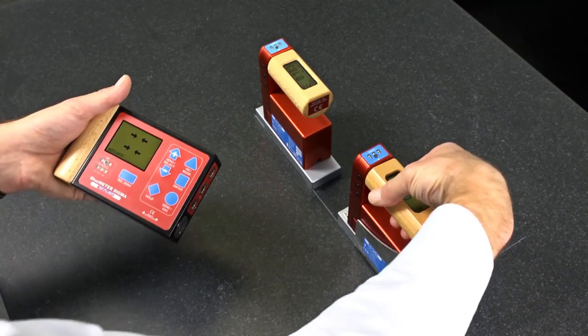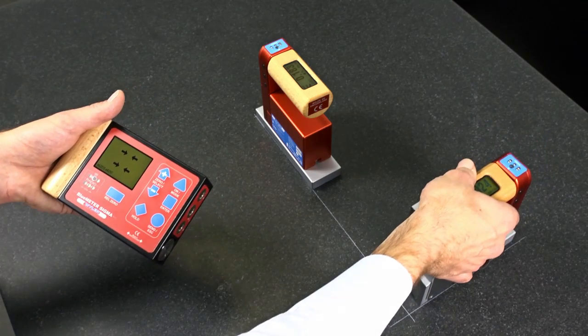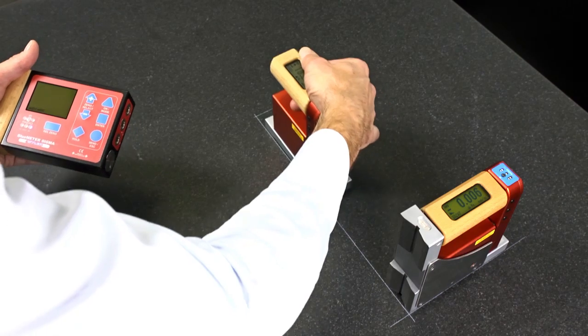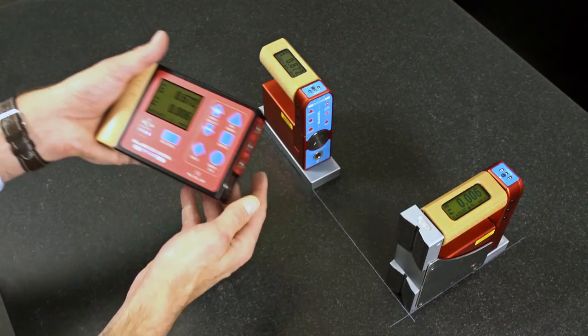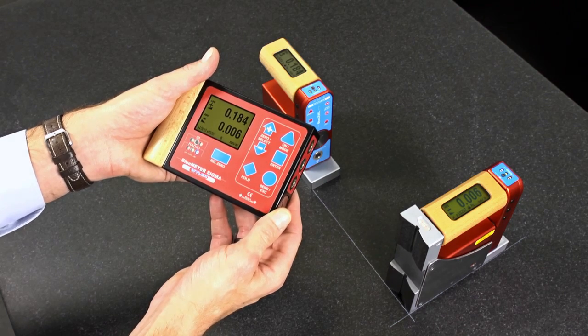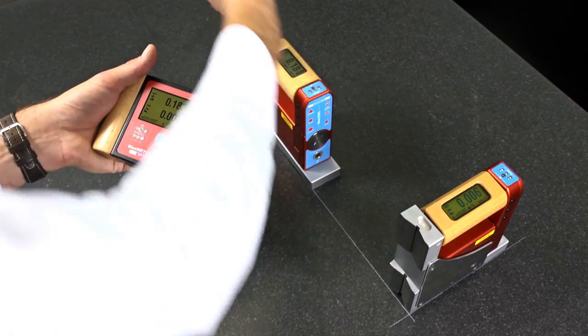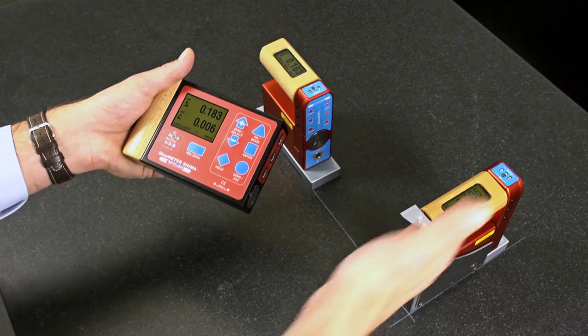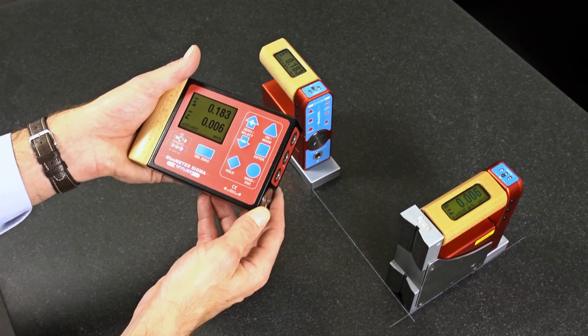The zero offset of the measuring instrument has been eliminated and I'm now positioning the blue levels in the desired measuring axis. I can see that I have to adjust my setting plate in the X direction by 183 micrometers per meter and in the Y direction by 6 micrometers per meter.